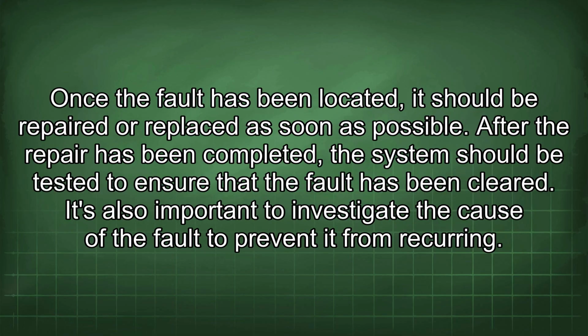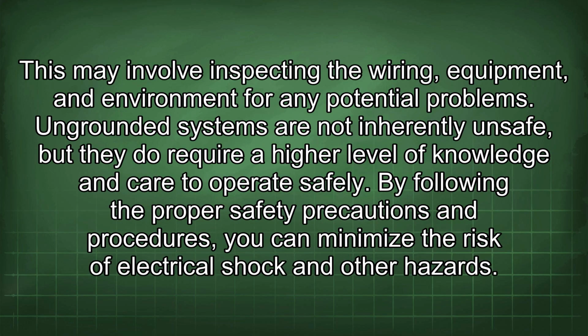Once the fault has been located, it should be repaired or replaced as soon as possible. After the repair has been completed, the system should be tested to ensure that the fault has been cleared. It's also important to investigate the cause of the fault to prevent it from recurring. This may involve inspecting the wiring, equipment, and environment for any potential problems. Ungrounded systems are not inherently unsafe, but they do require a higher level of knowledge and care to operate safely.